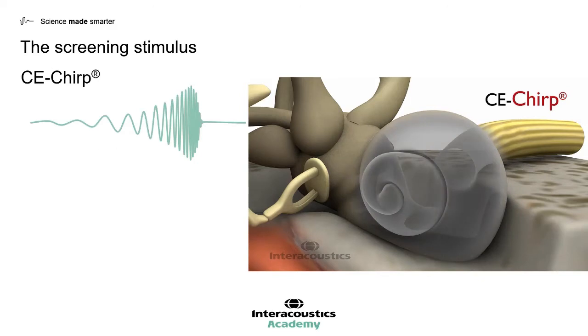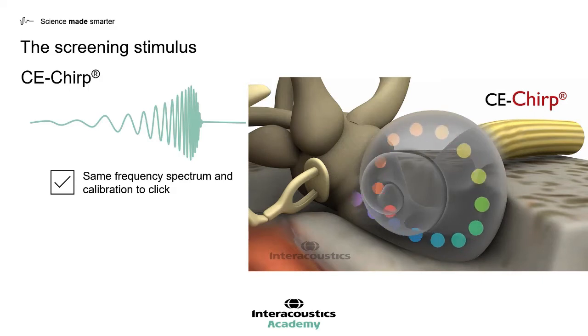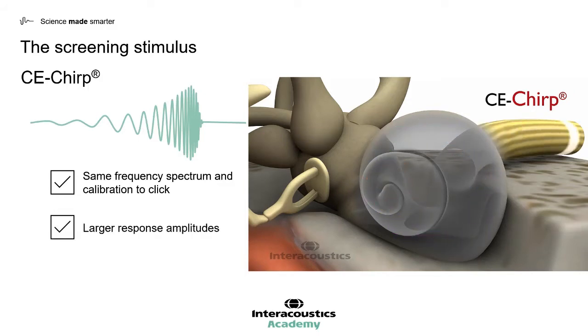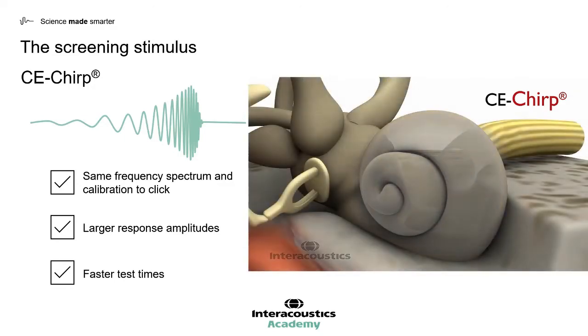A solution to the click stimulus has been found within the CE CHIRP. The CE CHIRP contains the same frequency spectrum and calibration as the click stimulus. However, it provides larger response amplitudes, and as a consequence provides faster test times.